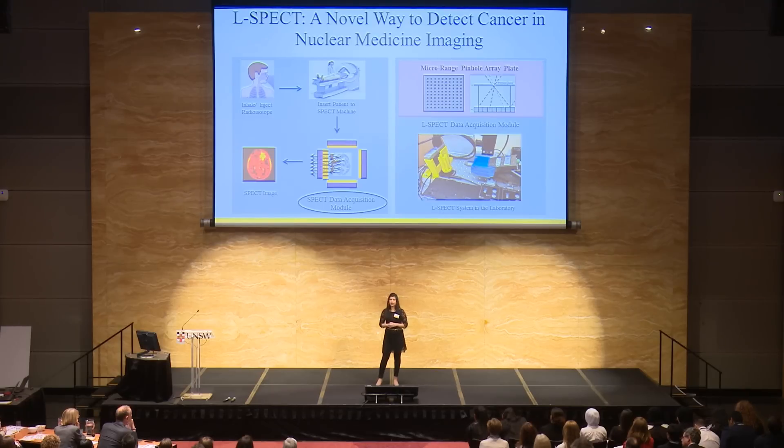That makes SPECT very low in acquisition. In my L-SPECT system, I'm using a micro-range pinhole array plate, which has 10,000 pinholes in total in a small active area. That can capture every possible ray from every possible direction, making the acquisition high. Because of that high acquisition, L-SPECT can collect sufficient data in a short span of time.